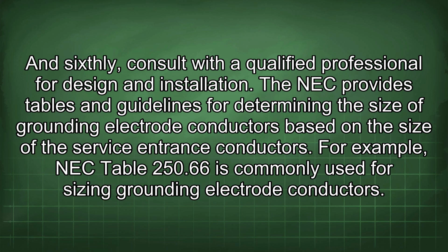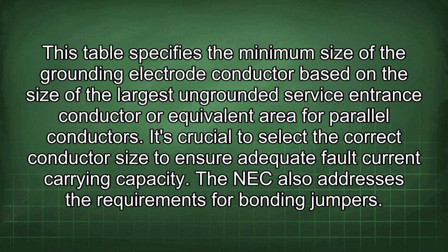NEC provides tables and guidelines for determining the size of grounding electrode conductors based on the size of the service entrance conductors. For example, NEC Table 250.66 is commonly used for sizing grounding electrode conductors. This table specifies the minimum size of the grounding electrode conductor based on the size of the largest ungrounded service entrance conductor or equivalent area for parallel conductors. It's crucial to select the correct conductor size to ensure adequate fault current carrying capacity.